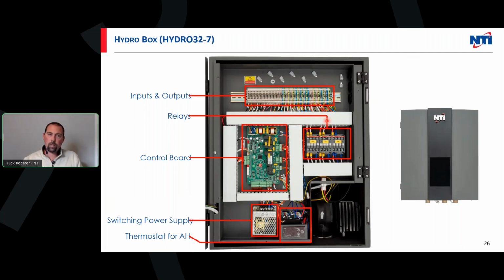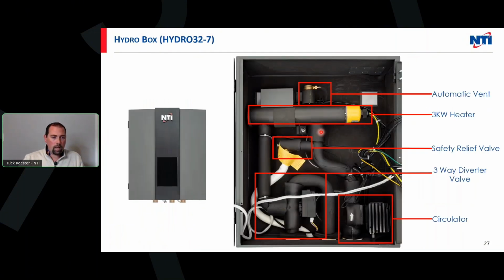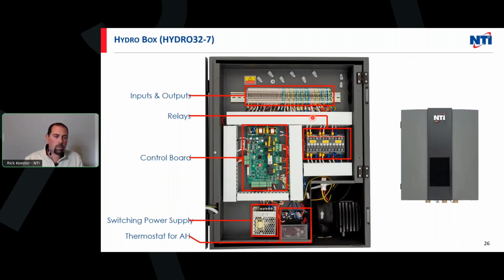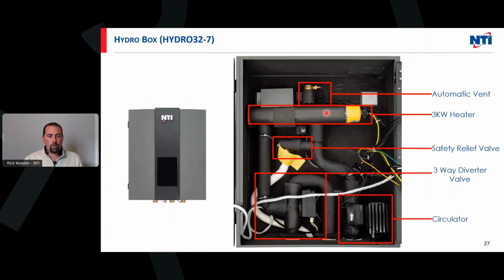The hydro box is just a little bit different. Dimensionally, it's a lot different, size-wise, weight, and all of that. We have the same inputs and outputs at the top here, same control PCB, same power supply. We do have an additional set of relays here and a thermostat for the auxiliary heating for that 3 kW element. That is standalone, with wires for everything we need to connect to it if needed. And I'll point this out, as you can see on the right, there are 2 hinges here, so this door is just going to open up and give you access to the 3 kW element. We have an air vent up here with a nice clear vinyl hose that runs through the bottom of the box. So God forbid anything happened to this air vent and there was any discharge of water, it's not going to happen inside the box. We do the same with the relief valve, which also has a discharge tube here that could be converted over. There's a fitting at the bottom. You could convert that over with some adapters to maybe copper or something and bring that down to the floor. We have a 3-way diverter, and here's our PWM circulator on the right-hand side.